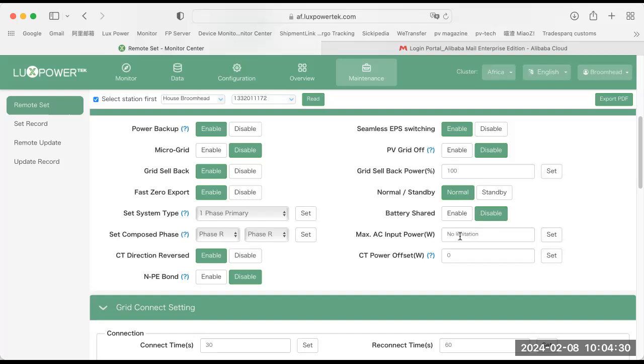Now remember that the 5 kilowatt can do 40 amps AC feed bypass current. The 12 kilowatt can do 90 amps, and the 10 I'm not really sure, but we can just check it up on the specifications. And then you set this limitation here to the value of your feed breaker. That means that when you're running bypass loads and you're charging the battery off grid, the combined value of those 2 loads will never exceed whatever you put inside here. And that simply means that you don't get a nuisance tripping on your feed breaker.